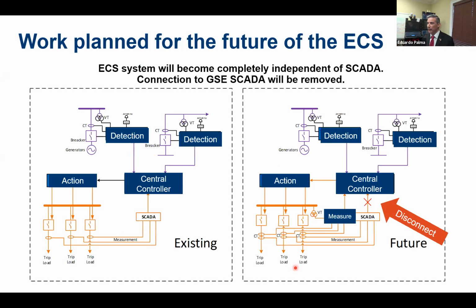That's my point. Going now to the future of the ECS system, or the emergency control system. As Alexander has just explained, they wanted to keep it separate, but there is some information from the existing SCADA that is being shared into the controller in order for the controller to take action. The plan in the future is to disconnect the SCADA and have the central controller hardwired to those measurements that are coming from the loads. Would you like to add a couple of comments? Yes. Okay, may I say?